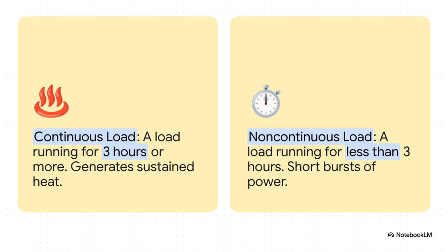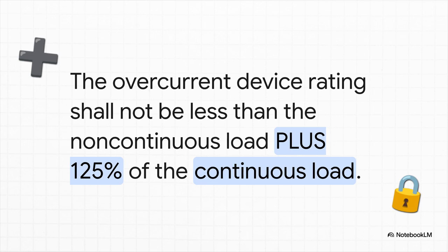So why does this distinction even matter? Well, it's because continuous loads generate something really insidious: sustained heat. And when it comes to electrical wiring, heat is the ultimate enemy. And this brings us right to the rule itself. The NEC says that a circuit breaker can't just match the load you expect. No, it has to be rated for the full non-continuous load, plus 125% of the continuous load. That extra 25%, that little buffer, that is the absolute secret to safety.